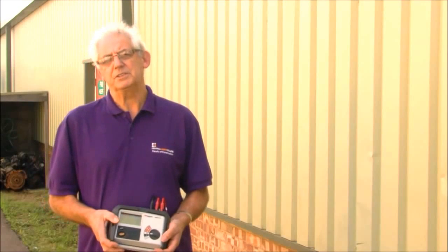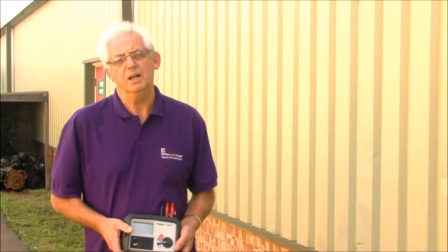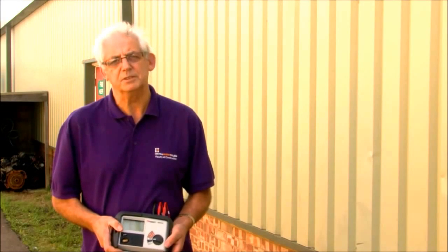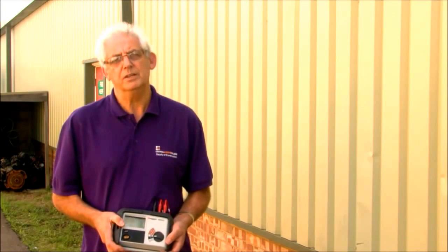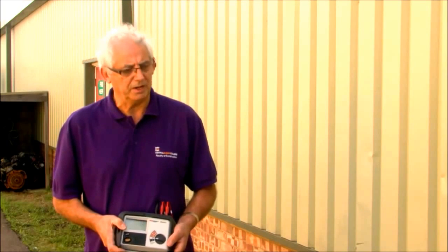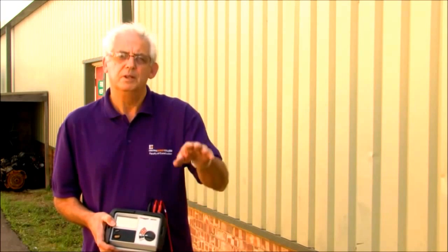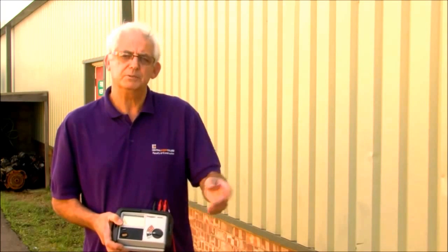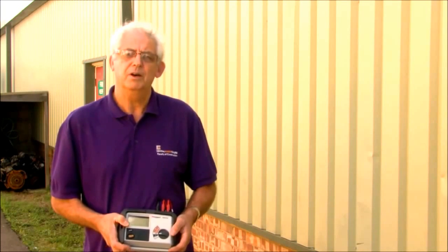If I'm working on an installation that requires a much lower earth resistance value, all I need to do is insert another earth rod. And the rules are that I would need to insert the earth rod the distance away from the original earth rod of whichever the depth of the original earth rod was. So we knew that this one's a 2 metre deep rod. I need to move 2 metres away and insert another one.